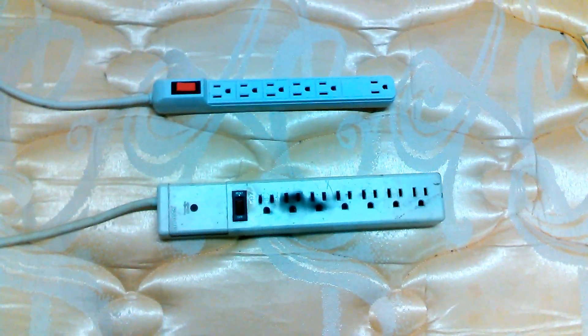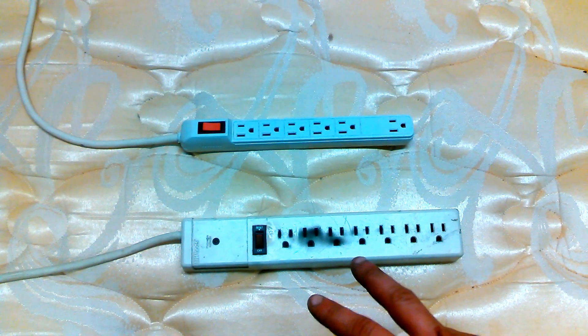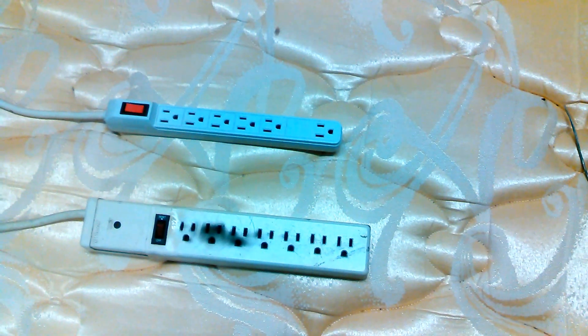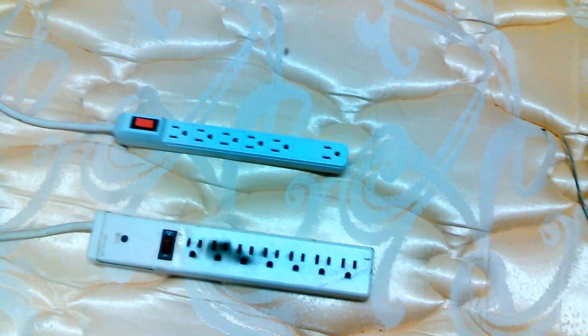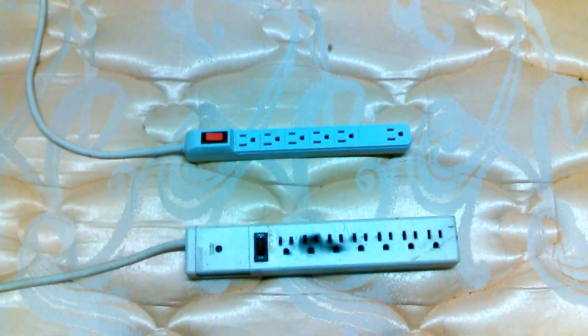I took it to work and took it apart, so unfortunately I can't show you. But there are two other surge protectors in this house that have blown up. What caused this was an open neutral.